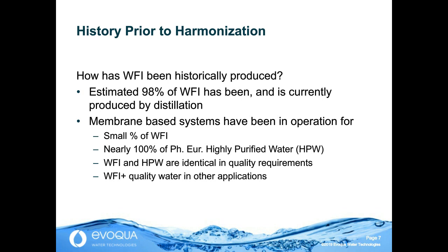Now, it's not fair to say that no membrane WFI systems exist. They do. A small percentage of the legacy systems are membrane. But when Europe introduced highly purified water in 2002, that specification is identical to WFI in water quality attributes. There was not the distillation requirement. So nearly 100% of HPW systems that went in were membrane. They had a great success record. That is a big part of Europe modifying the regulations to allow alternatives to distillation. And in other markets, we'll take a quick look to see that in markets outside of pharmaceutical, membrane systems are dominant and there are virtually no distillation units in some other high purity markets.